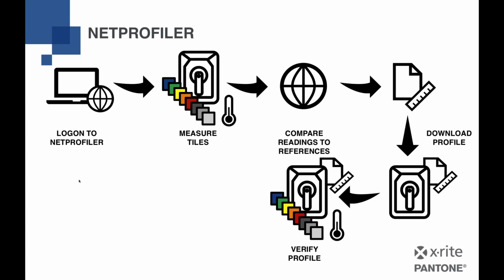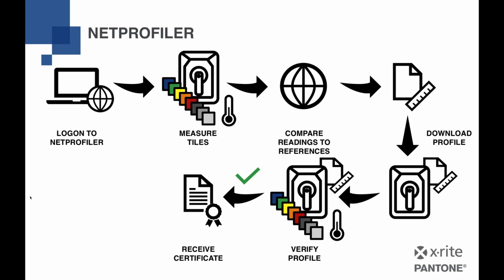Now, once you have loaded that profile onto the instrument, you make a verification measurement on your tiles, again considering your current temperature, and if you see an improvement there, or if the server determines an improvement, you receive a certificate, which is more or less as good as a calibration certificate, with the benefit of telling you how well your instrument performs in your environment. And we'll see in a couple of minutes what environment means in that context.